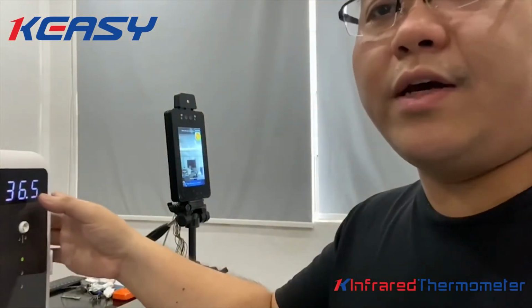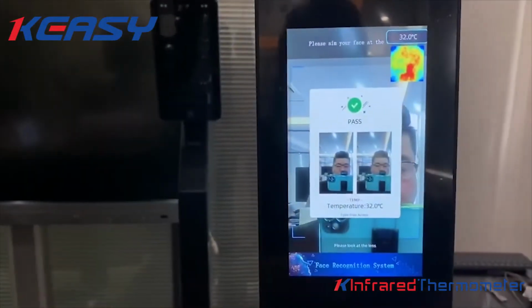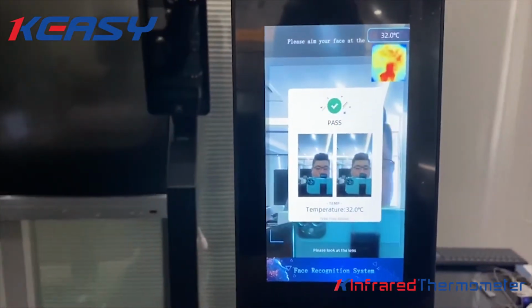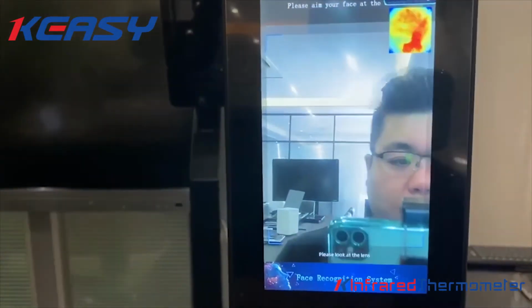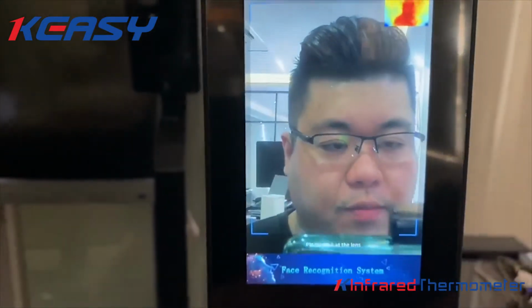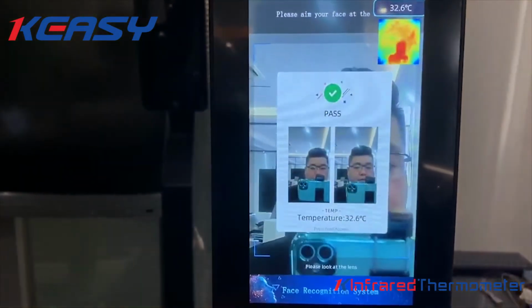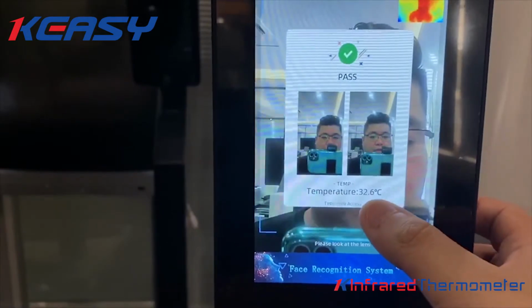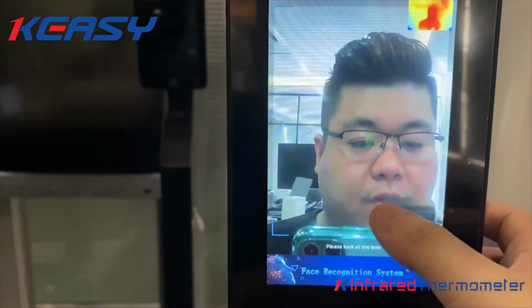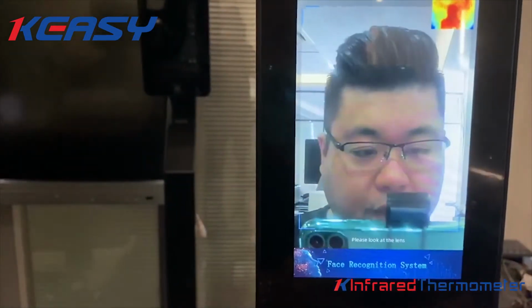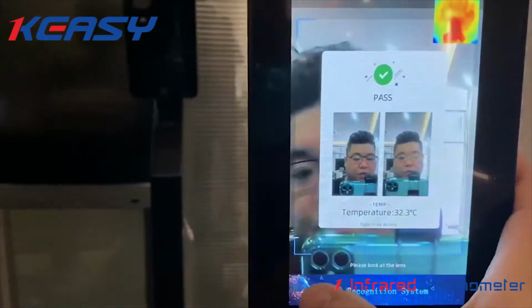Okay, so now my temperature is 36.5 Celsius. After the 10 to 15 minutes, now we can start to measure our temperature from the 7-inch device. And now you can find that my temperature is lower than the thermometer I tested. So we need to start to do the calibration.